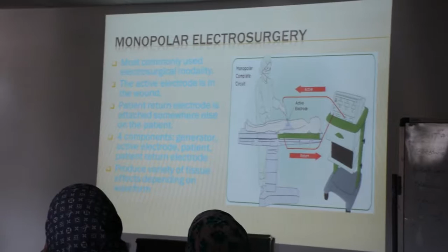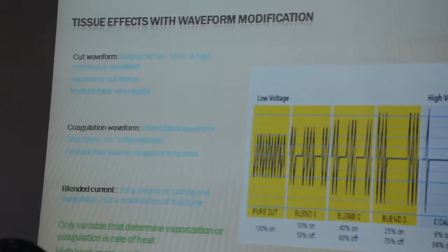Cut waveforms: duty cycle on time is high, a continuous waveform. It vaporizes or cuts tissue very rapidly. Coagulation waveforms: alternating, intermittent waveforms, duty cycle on time reduced, produce less heat so coagulum is formed. Blended current is not a mixture of cutting and coagulation, but a modification of duty cycle. The only variable that determines vaporization or coagulation is the rate of heat. High heat, more rapid vaporization; low heat, more slowly coagulum.